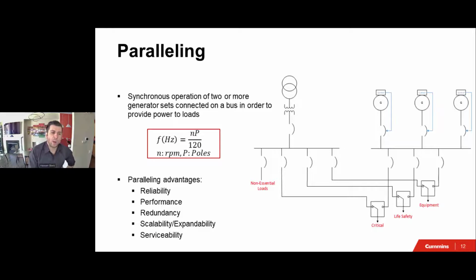You might say, okay, what are the advantages of paralleling? Obviously, the performance. The more generator sets you have connected to the bus, the stronger, the stiffer the bus, and the more you'd look like a utility. It's easy to create what's called an N+1 or redundant system. All you have to do is add 1 or more generators. Serviceability: hopefully, you're doing regular maintenance on the generators. For example, if you have 1 generator and you want to take it down for maintenance, you don't have backup power. So this is why you want to resort to adding 2 or more generator sets, and obviously reliability.